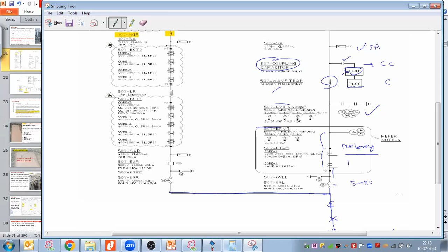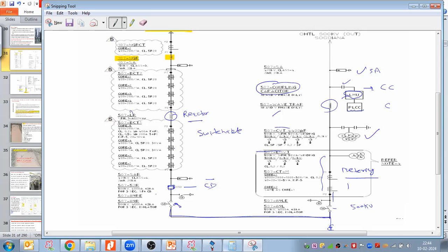And then I'm taking tappings from this conductor, and then I'm connecting here the reactor, which you can see here, LR, line reactor. This is my reactor that we discussed, and it is connected with the help of the disconnector and earthing switch, because we require the maintenance of this breaker. This is the circuit breaker here. I'm using a circuit breaker. Why? Because I wanted to make this reactor a switchable reactor, right? So whenever I require to switch on the reactor in the system, I can close the circuit breaker. Whenever my system is running on full capacity, I don't require the reactor, so I can switch off this reactor. To make it switchable, I use the dedicated circuit breaker here.